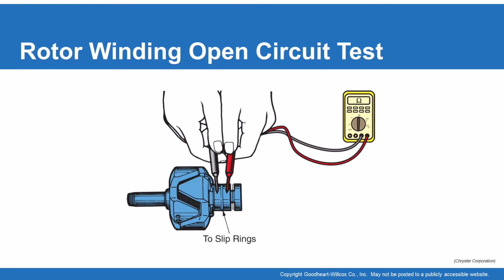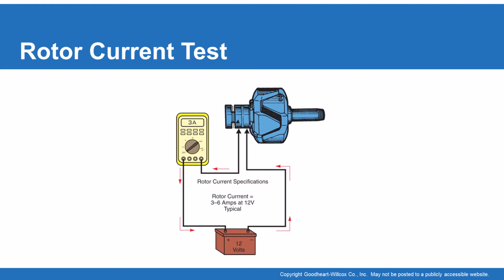Here's another image of a procedure that you could use, and again, we would be doing the rotor winding open test here. So when you actually touch these two parts, what would you expect to see? That's correct. You should see continuity here, just not with the ground shaft. If you didn't, then that would mean that we have some kind of open in that rotor winding.